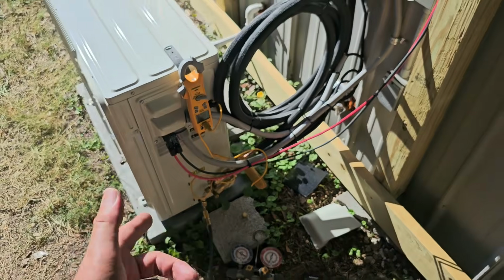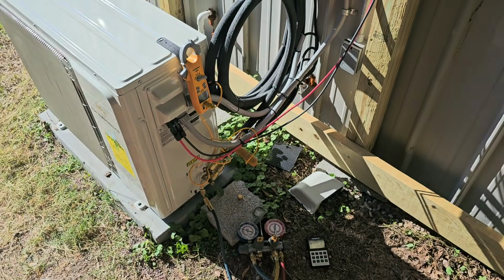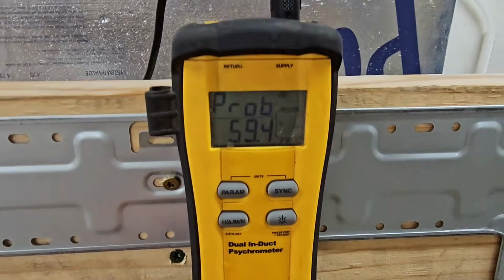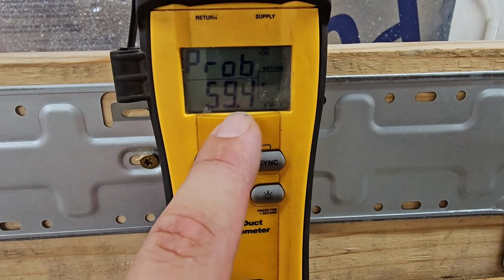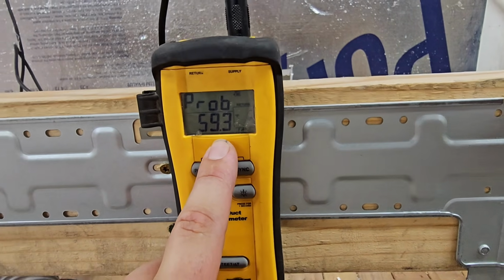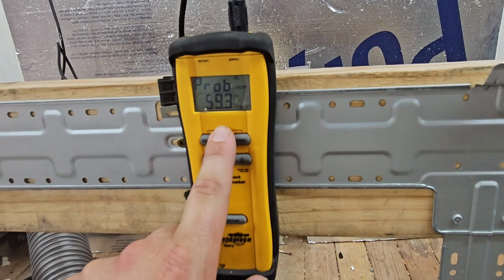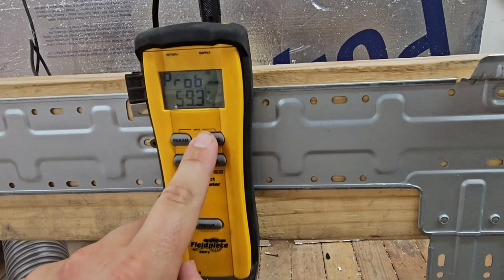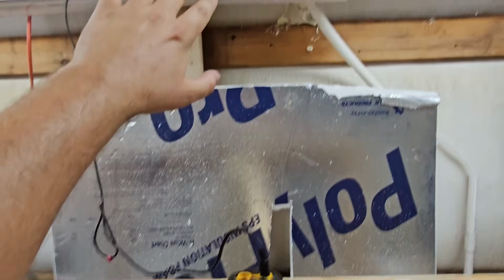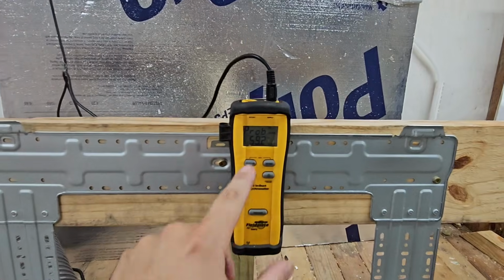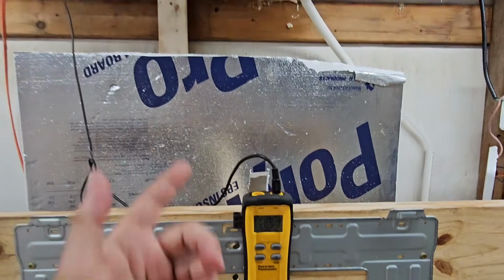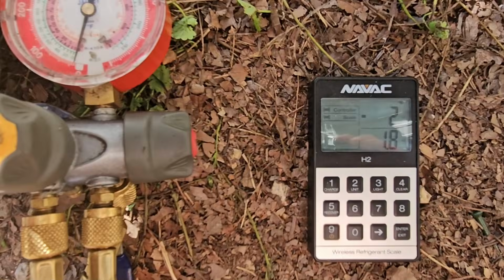Before we do that, let's check out the supply air temperature again. Measuring the supply air temperature once again, it's 59. Before it was in the 60 range, right? So we lowered that temperature by adding refrigerant. It actually feels better. So 59, but we're not there yet. Let's get there. Time to add some more refrigerant.